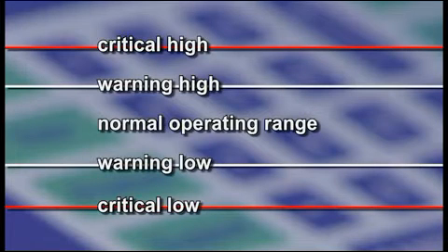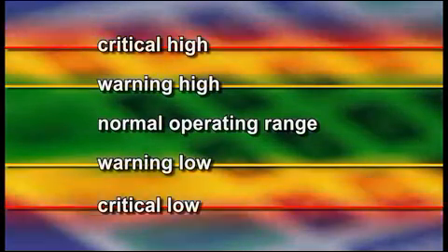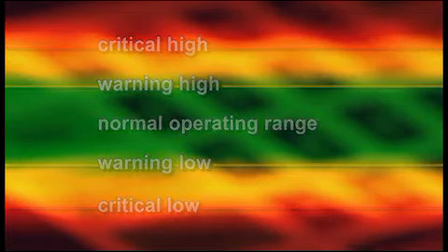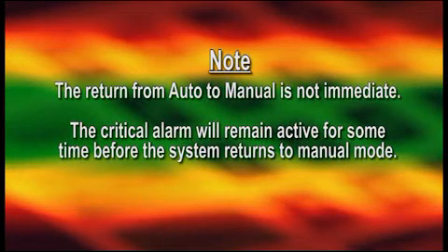For each alarm limit, there are 2 stages of alarm. The first stage is a warning alarm, and the second stage is a critical alarm. The warning alarm tells you there may be a problem, but the Dryer Master will attempt to correct the problem. If the Dryer Master cannot correct the problem, a critical alarm will be reached. This will return the Dryer Master to manual or local mode.